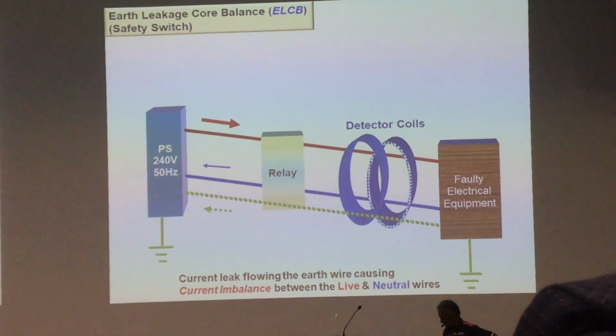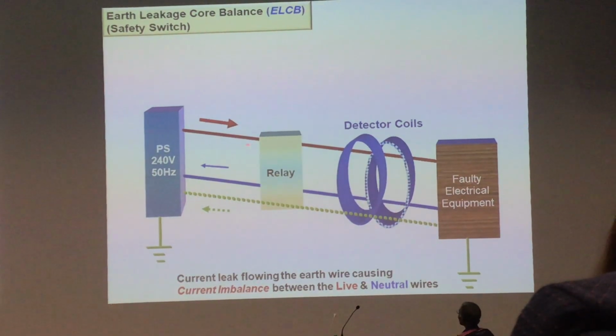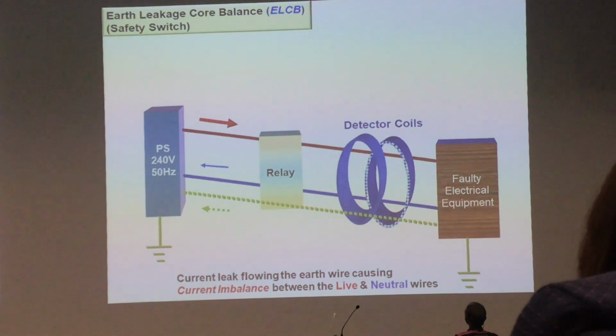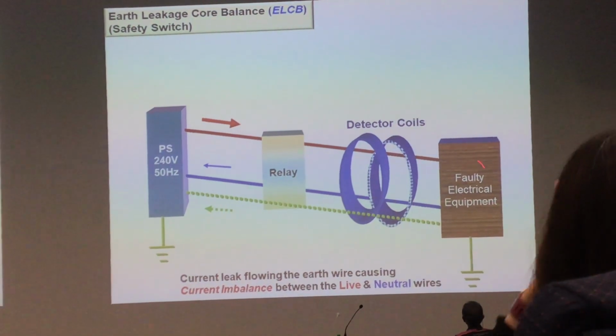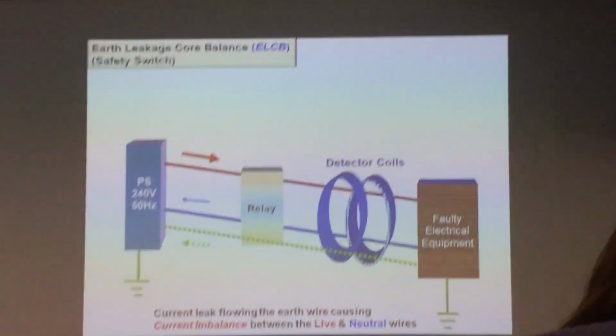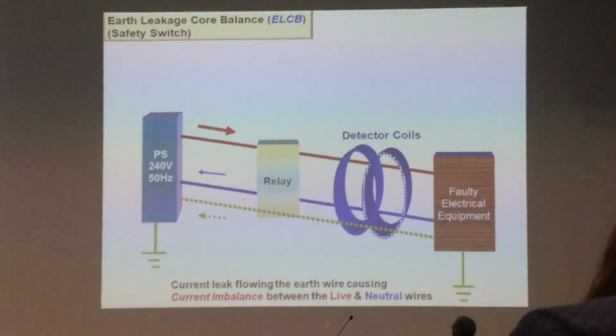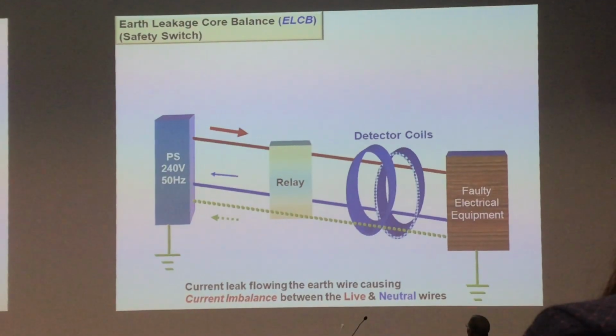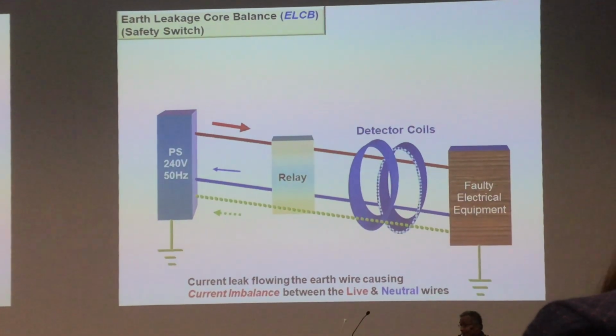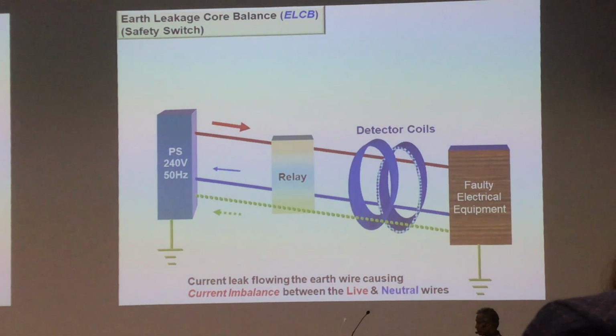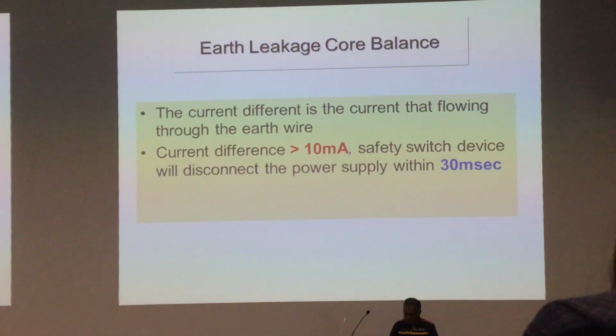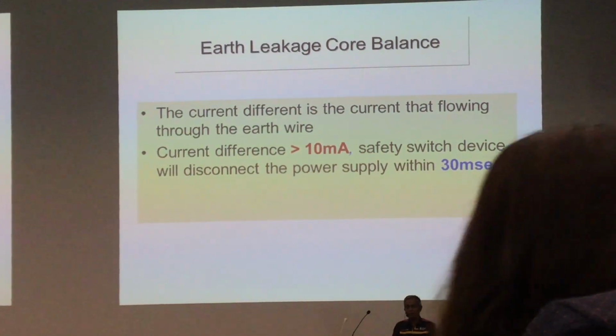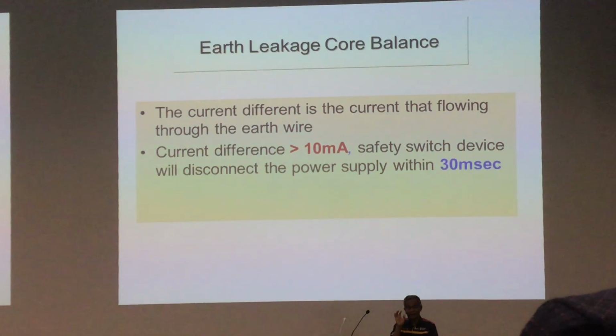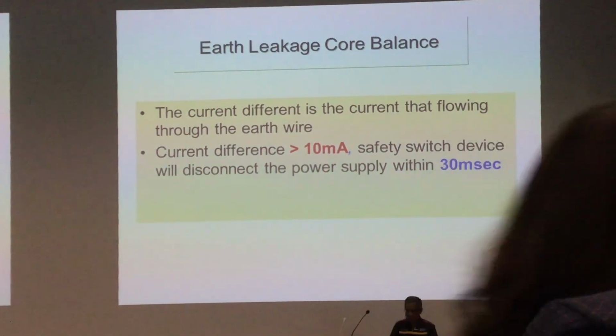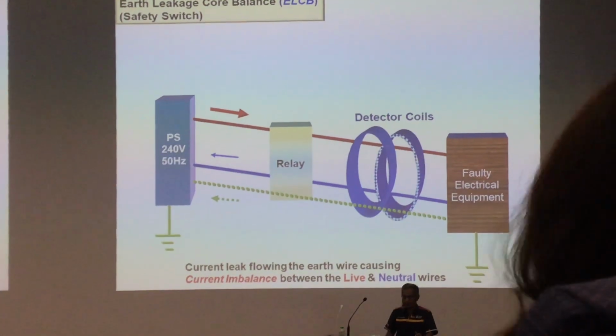Let's say the same system, current going in and going out, but the machine is faulty. Going in 10, going out 9.8, for example. The difference is 0.2 amp, so this system will be disconnected automatically, because 0.2 amp is big. Earlier I mentioned it detects as little as 10 milliamp, and 1 amp is 1000 milliamp. So this is a good mechanism to protect the user.